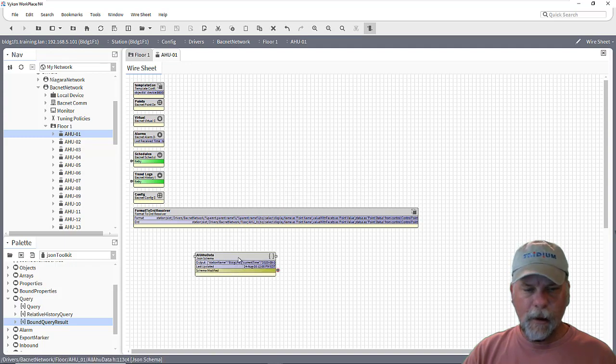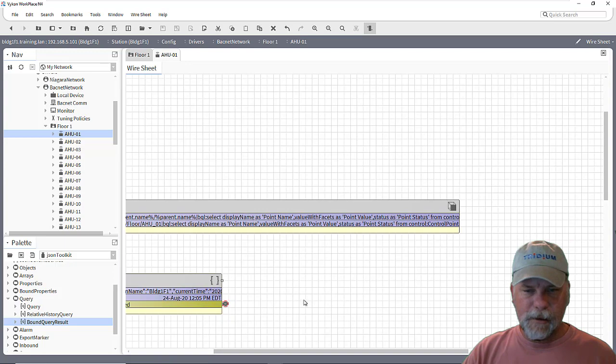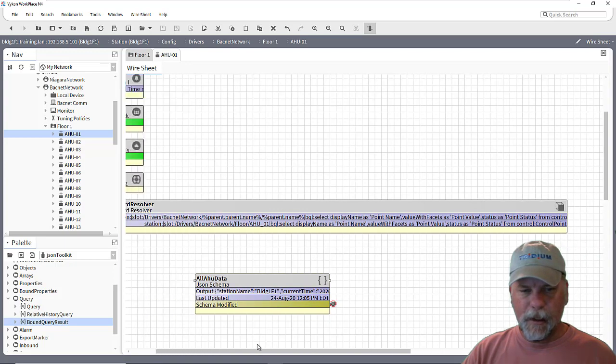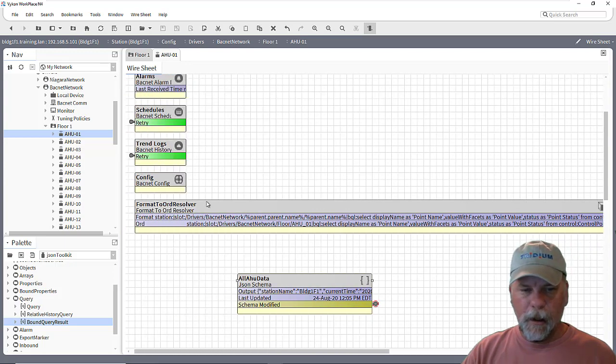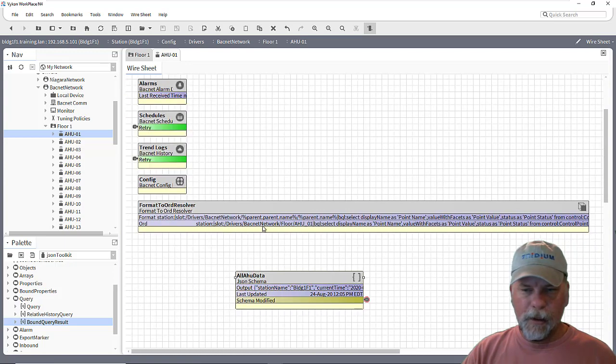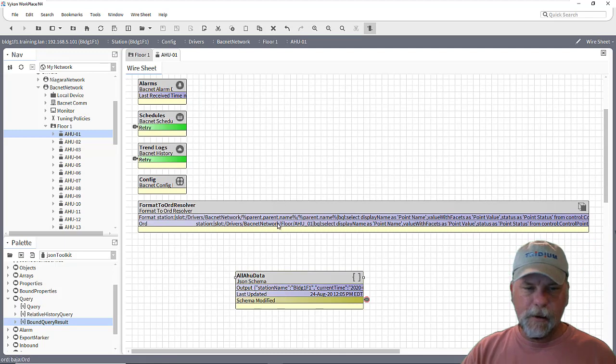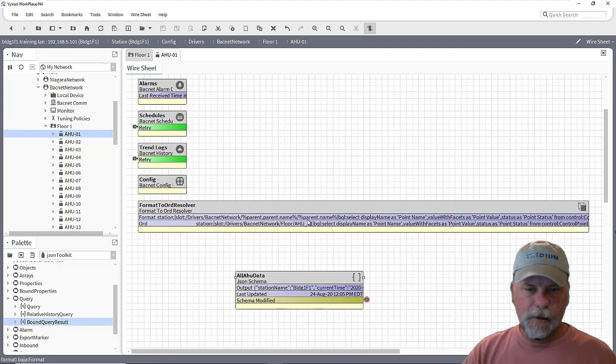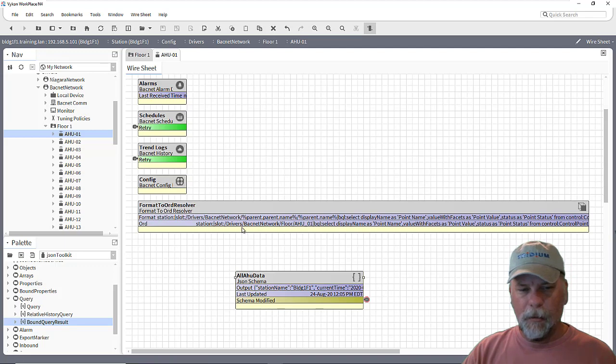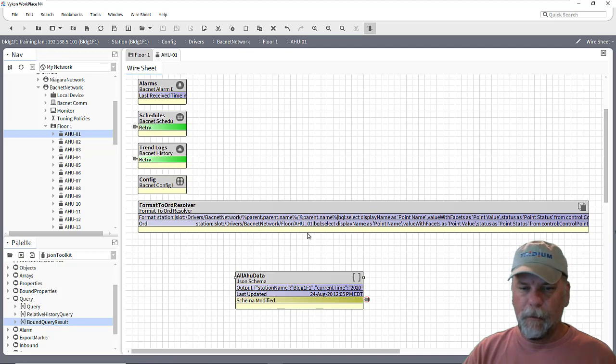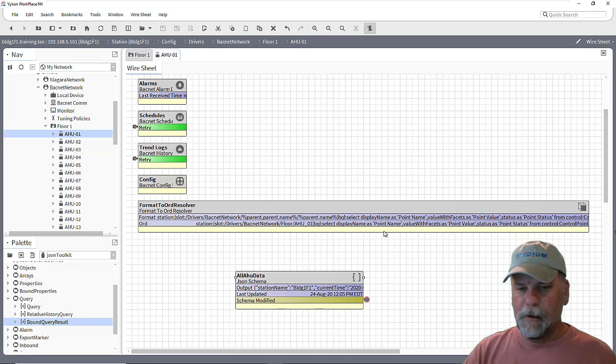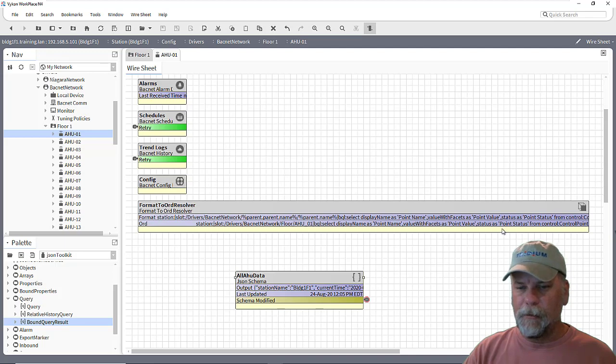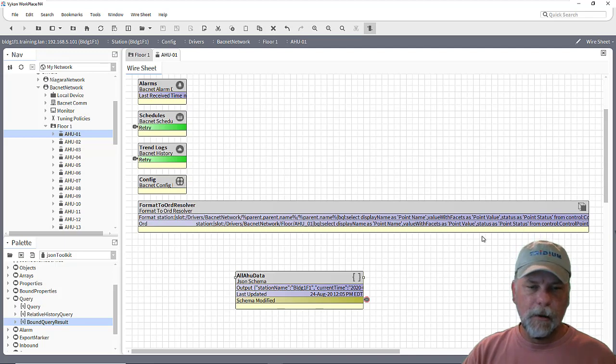What I've done here is actually using a custom component, but this component is using a B format script syntax to come up with an actual Ord that might be the BQL query to limit the scope to AirHandler 1 and then select the display name of the point, the value of the point, and the status from control points.